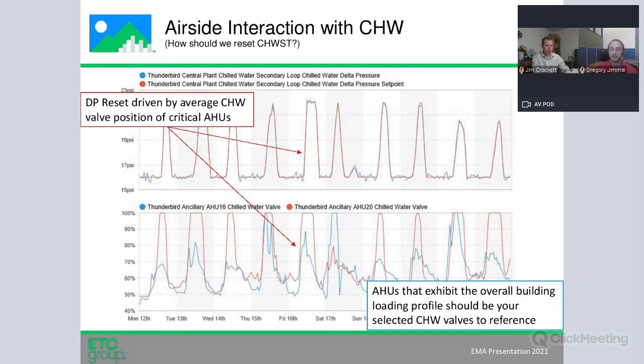So then you may be asking, well, what valves do I look at? How do I go about resetting my differential pressure? This is a little bit deeper of a dive on seeing the interaction there. This is, again, at a hospital in Phoenix. So you'll see these valves increasing up to 100% during the peaks of the day, and the differential pressure responding accordingly to satisfy their cooling demand.